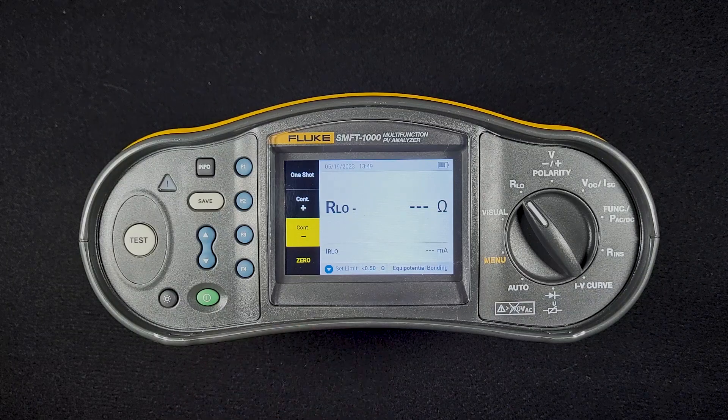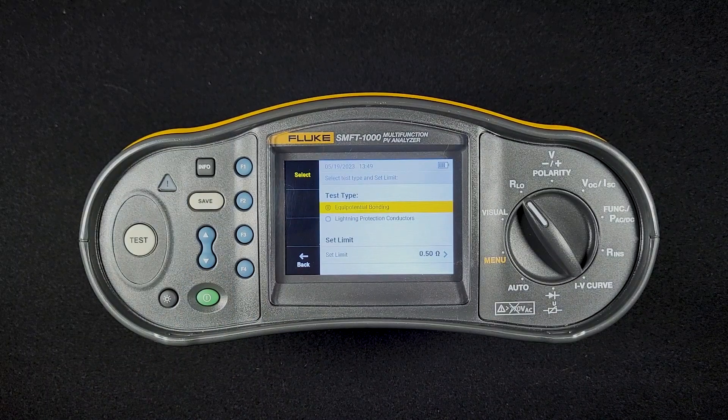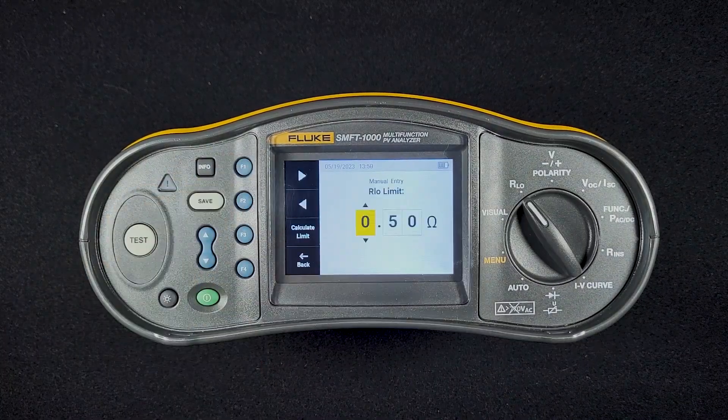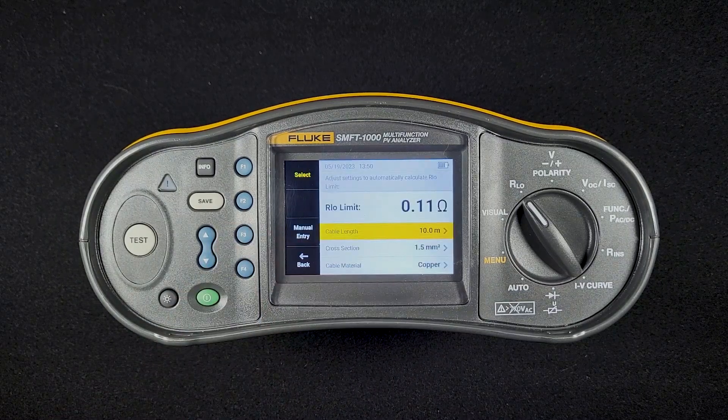You can also set the limit for what's passing and what's failing by hitting the down button. I have this set for half an ohm. That's the ANSI/NETA maintenance testing standard limit for a passing resistance test for two pieces of non-current carrying metal parts bonded together. You can also have the device set the limit. Go down to set the limit and hit select. You can either manually put it in or have the SMFT-1000 calculate the limit based on the length of cable, what type of wire we're using, and the cable material, whether it's copper or aluminum.